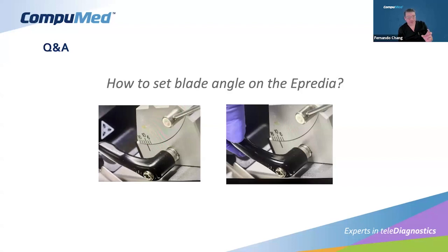Look, with a millimetric ruler you can do that. So the next millimetric equal distance will be 4. I'm not saying that this is ideal, but it's better than just guessing 5. And if it's not possible, you still can cut it at 6. It's not a big deal. But that's how the Epredia cryostat angle can be set. Okay, so go ahead, Laura.